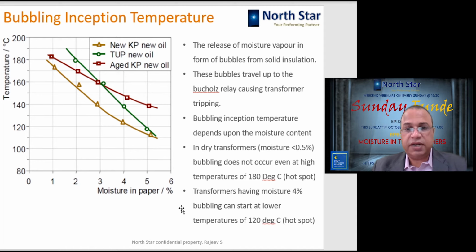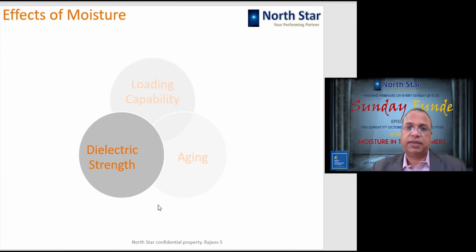Okay, so if a dry transformer is there, as I said, up to 180 degrees centigrade no bubble will form, so your transformer will keep on working even if you are loading it to, of course, hotspot temperatures we are talking about here, 180 degrees centigrade, nothing will happen. But if the transformer is wet, if say 4% moisture is there, then around 120 degrees centigrade itself it will start bubbling, so you will not be able to put more load on this transformer, and this is how the loading capability of the transformer gets affected because of moisture in the transformer.